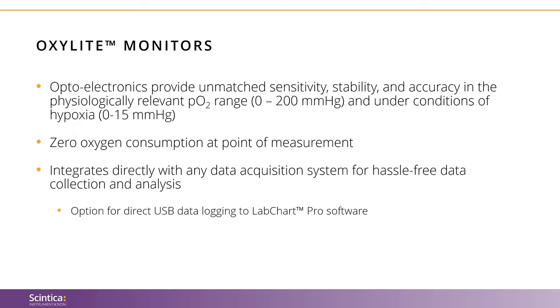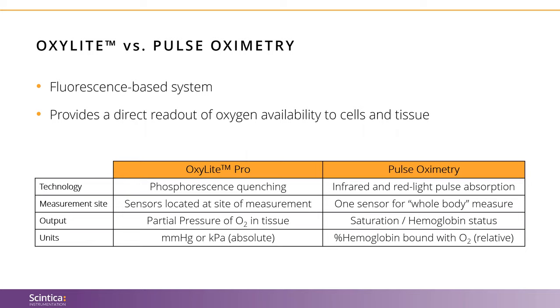We can quickly compare the OxyLite oxygen monitor with pulse oximetry. Pulse oximetry provides blood oxygen saturation — the percentage of hemoglobin saturated by oxygen — of the whole body, showing only hemoglobin status of the whole animal. In contrast, the OxyLite, which utilizes phosphorescence quenching technology, provides a direct readout of oxygen availability to cells and tissues. The OxyLite takes measurements from sensors located at the site of measurement recorded as absolute units of millimeters of mercury or kilopascals, while pulse oximetry uses one sensor for a whole-body measure with relative units measured as percent hemoglobin bound with oxygen.